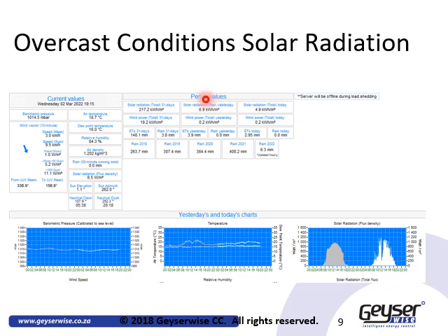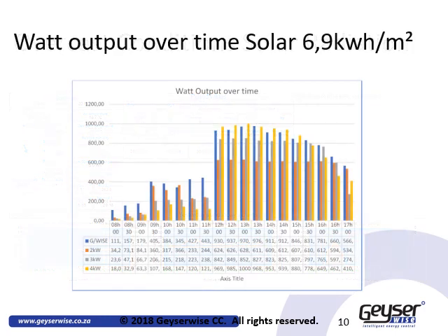On this slide we have the solar radiation values for the 1st and 2nd of March. During the next two slides we will illustrate the effect of fixed resistance heating elements versus variable resistance heating elements with the MPPT. On this day we had overcast cloudy conditions, and from this you will observe that the Geyserwise with variable resistive heating elements actually outperformed all of the others by far.